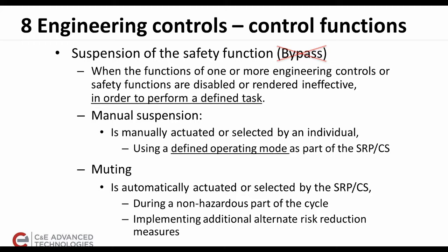We have also removed a term from the standard. We have taken bypass out because of its negative connotation, and the term now is suspension. Basically, under the mode of suspension, the safety function is disabled and is not in a position to eliminate the hazard. Other means are called in to use that.